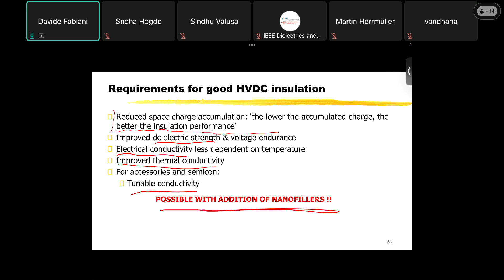There are also additional requirements that emerged very recently: the desire now is for not only better performing materials, but also more environmentally friendly ones. This is because cable manufacturers have to do the so-called life cycle assessment and eco-design of their equipment. XLPE is now the benchmark insulation used everywhere, but the problem is that XLPE is quite difficult to recycle because it's a cross-linked thermosetting material. Also, the degassing process necessary to remove the cross-linking byproducts is a very energy-consuming process.